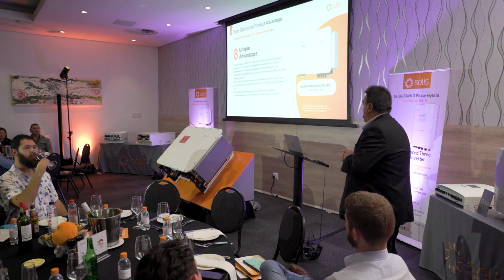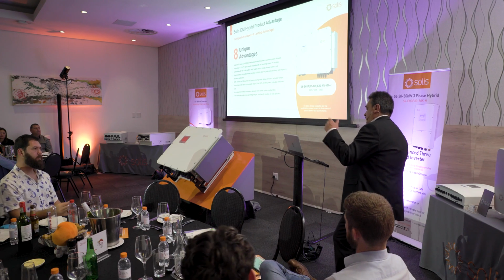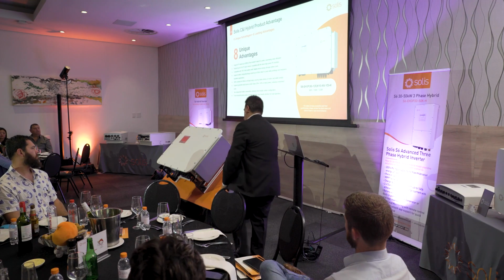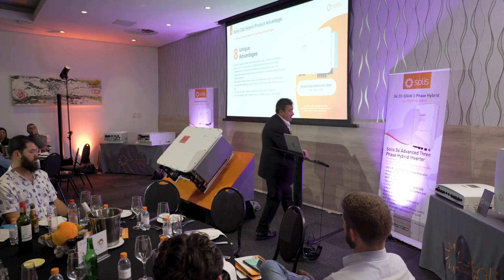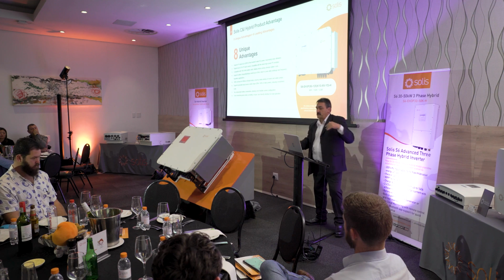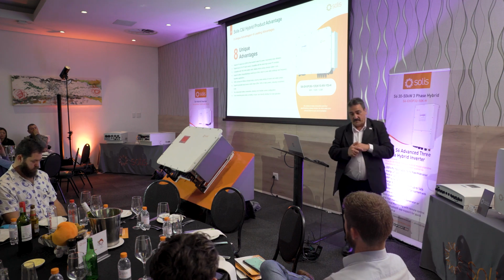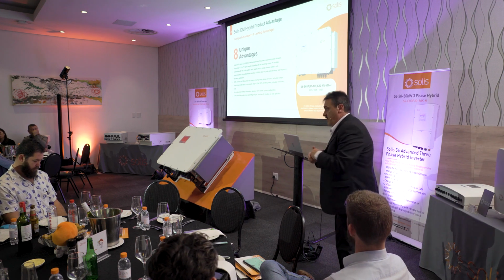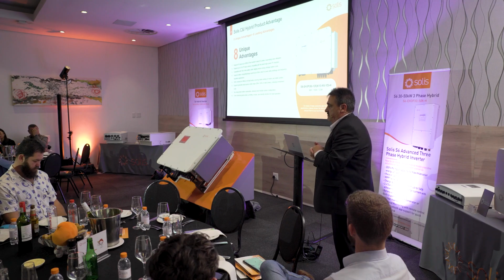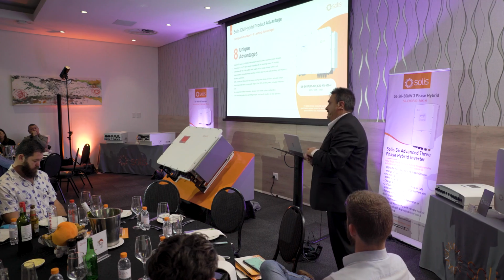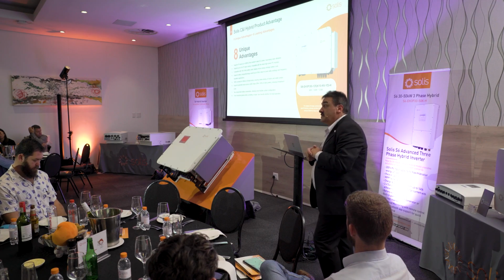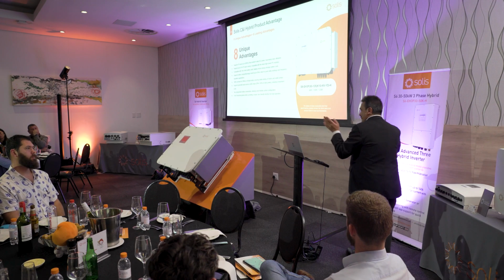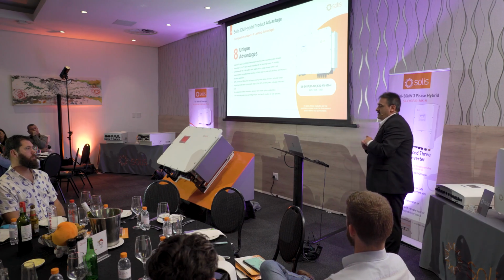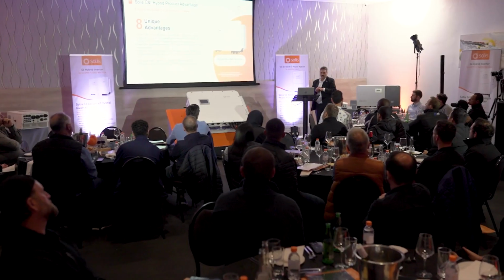You can run that second bank on the second port - one gives you 100 amps through one port, and another gives you 100 amps through the other. We actually run a system like that at the office: two 50 kilowatts in parallel with 3 different battery manufacturers between the two inverters, even at different voltage levels. It works, but it's not advised - it messes around a lot with the voltage systems, but it does work.